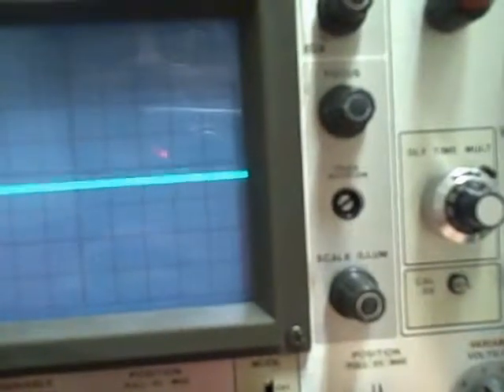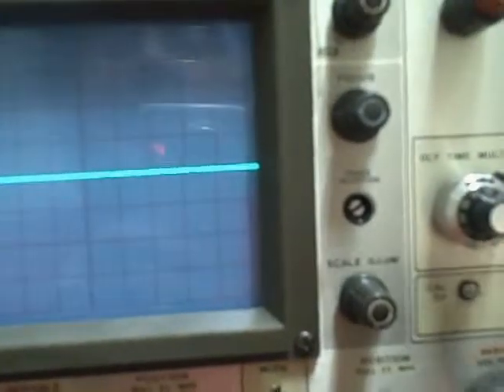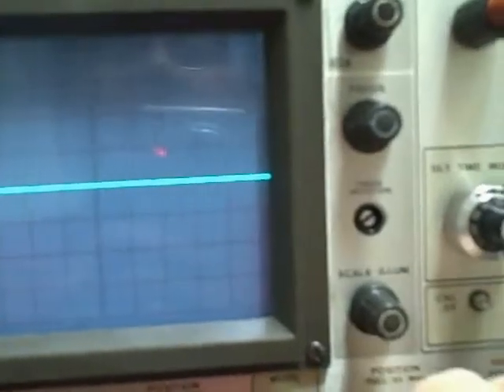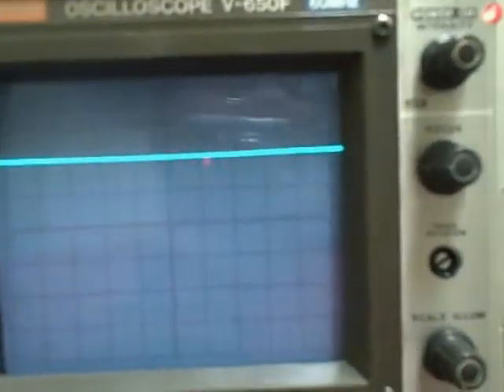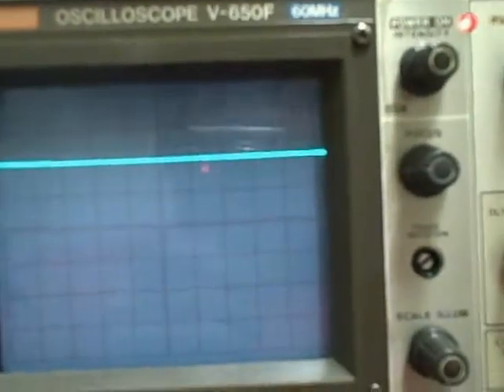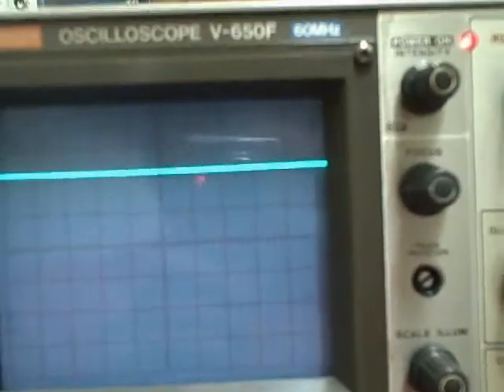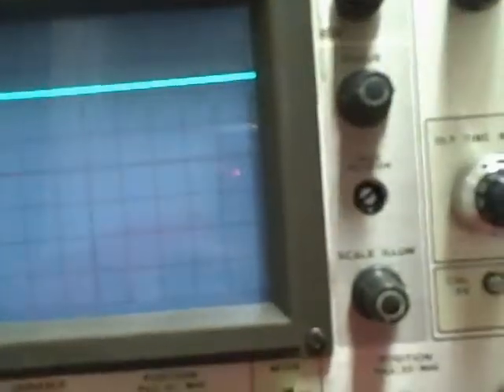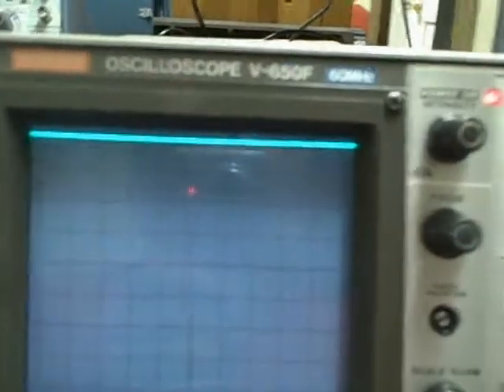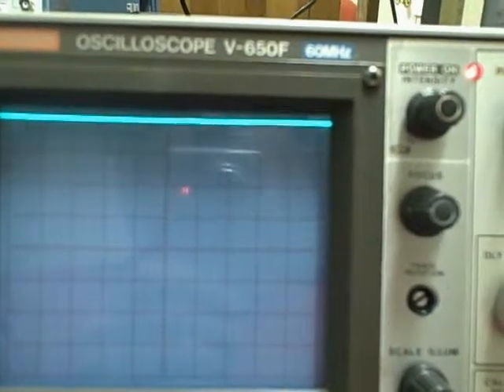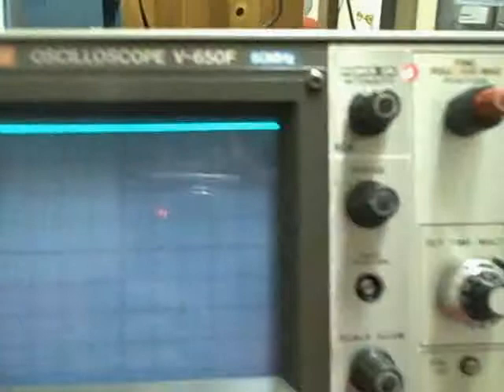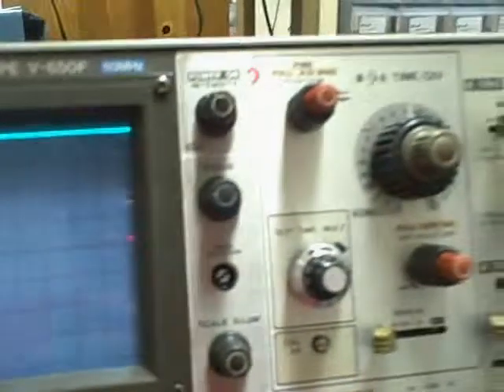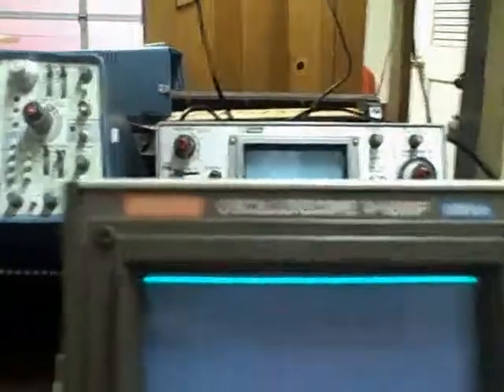Let's go ahead and take ourselves to 2 volts per division. Check the zero quickly. And there we are at 2 divisions, just like we should have been. And we raise that up to 4 divisions. 4 divisions, 2 volts per division, that's 8 volts, and we are running 7.96 volts. So we've done that.